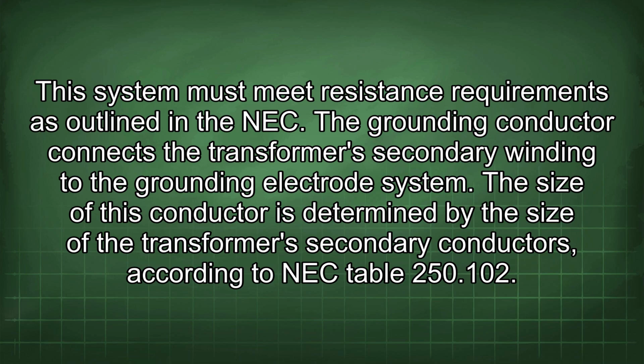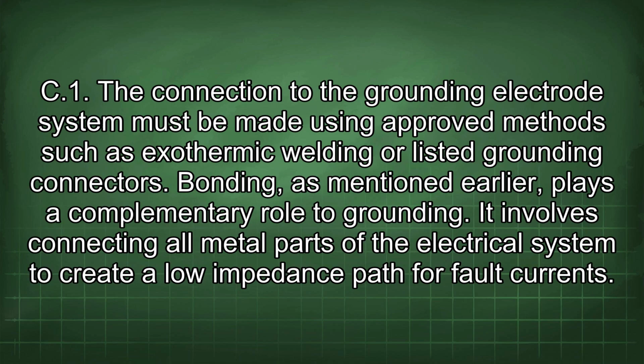The grounding conductor connects the transformer's secondary winding to the grounding electrode system. The size of this conductor is determined by the size of the transformer's secondary conductors according to NEC table 250.102(C)(1). The connection to the grounding electrode system must be made using approved methods such as exothermic welding or listed grounding connectors. Bonding, as mentioned earlier, plays a complementary role to grounding.